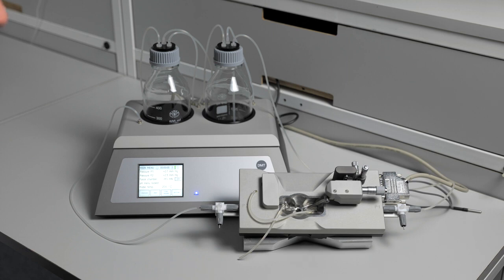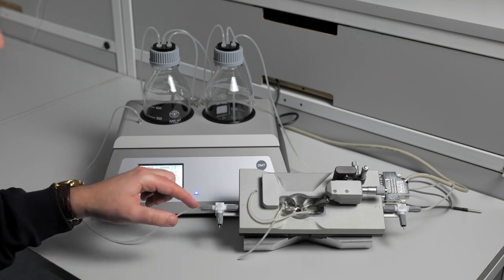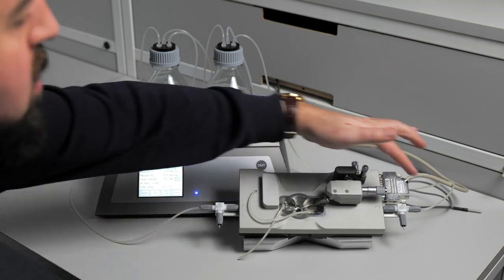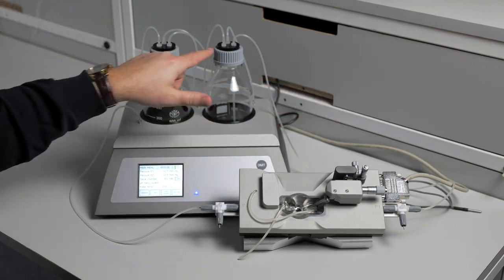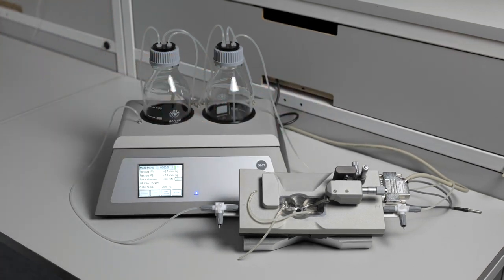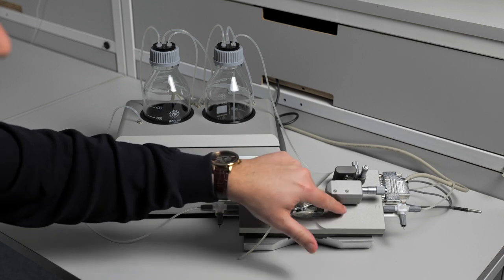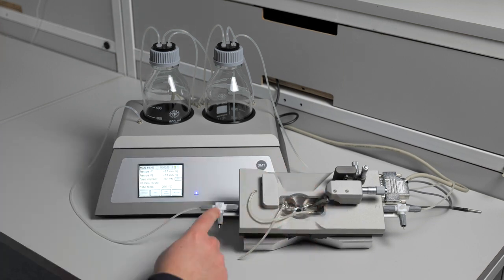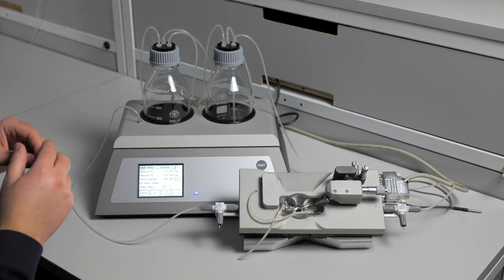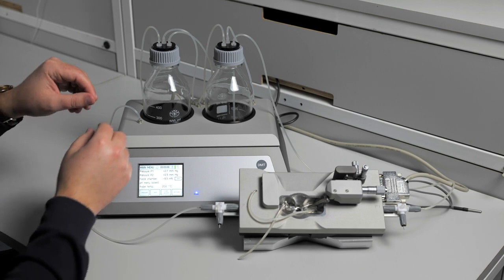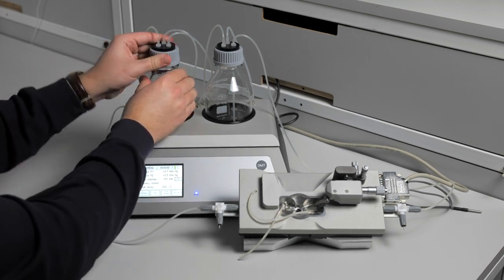The possible causes of a pressure leak are either cuts in the tubing along the system, the O-rings in the bottle caps, a blown pressure transducer inside the chamber, or the three-way valves on each side of the pressure chamber. Start by investigating the O-rings in each cap of the bottles on the interface.